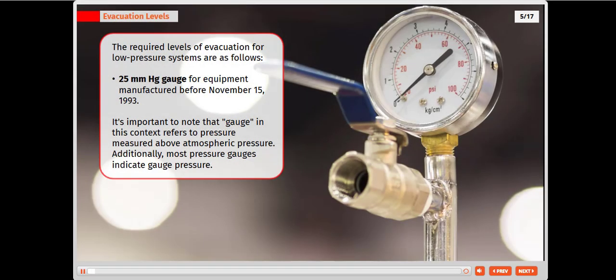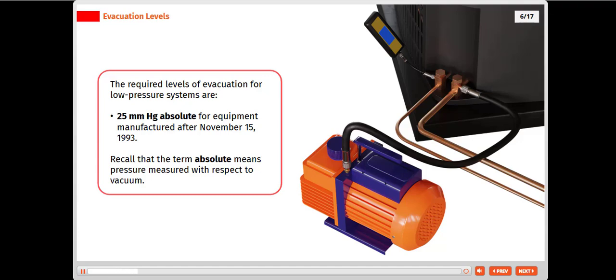The required levels of evacuation for low-pressure systems are as follows. 25 millimeters of mercury gauge for equipment manufactured before November 15, 1993. It's important to note that gauge in this context refers to pressure measured above atmospheric pressure. Additionally, most pressure gauges indicate gauge pressure. The required levels of evacuation for low-pressure systems are 25 millimeters of mercury absolute for equipment manufactured after November 15, 1993. Recall that the term absolute means pressure measured with respect to vacuum.